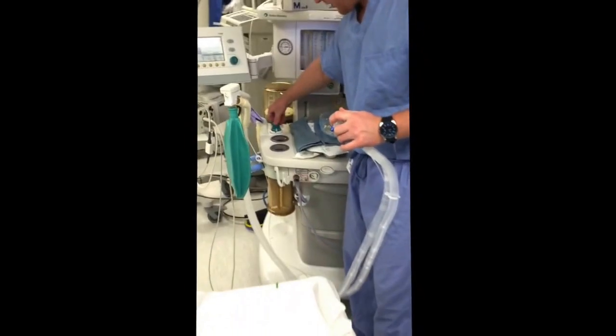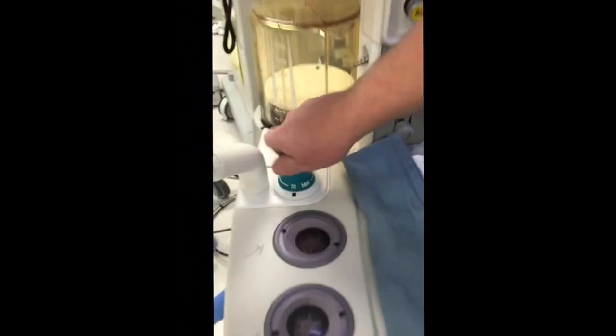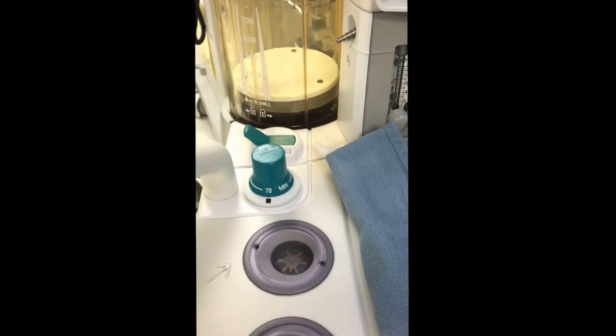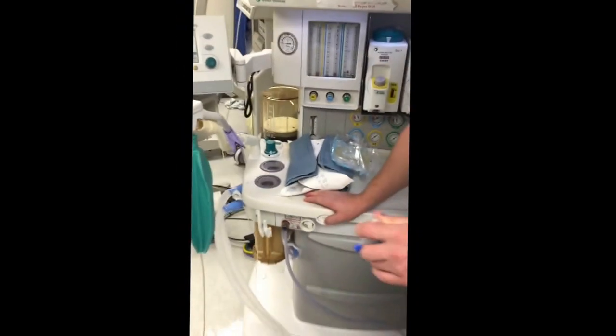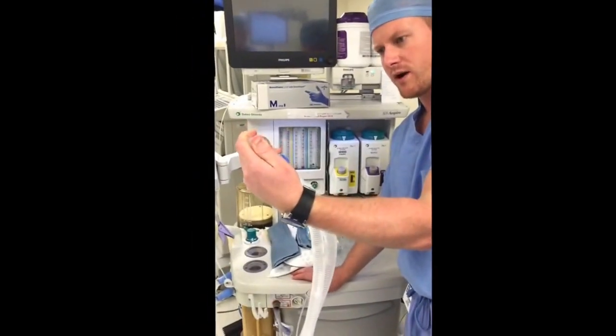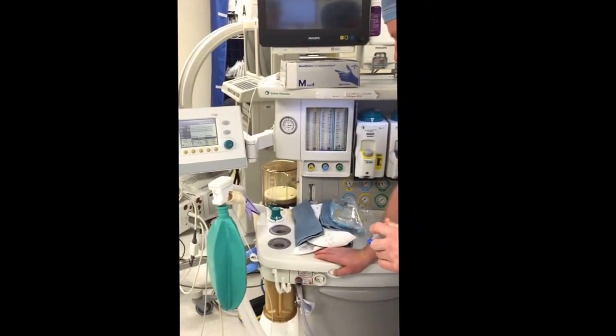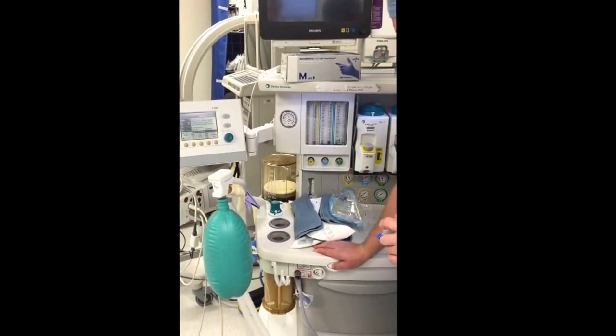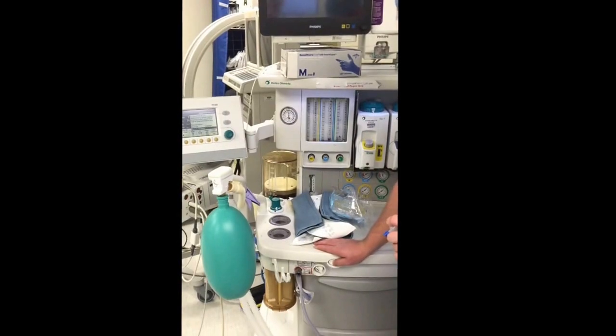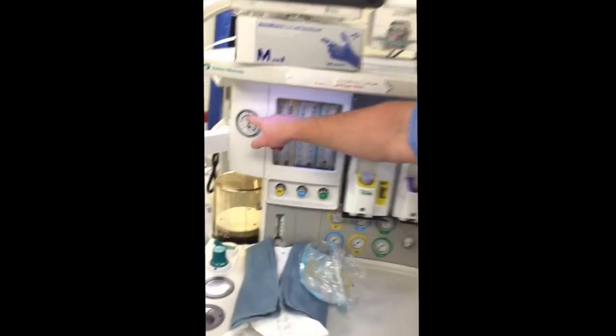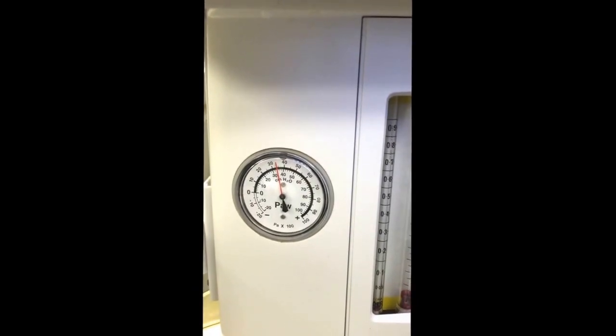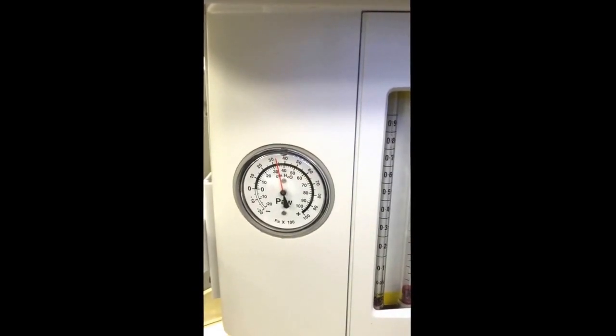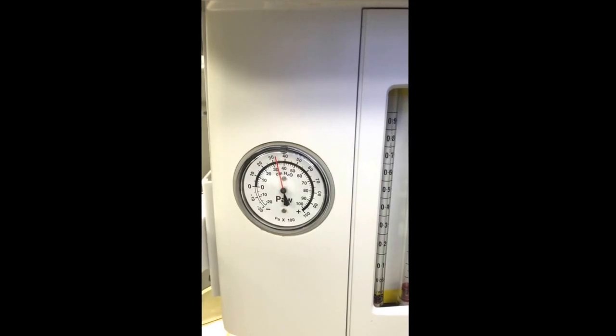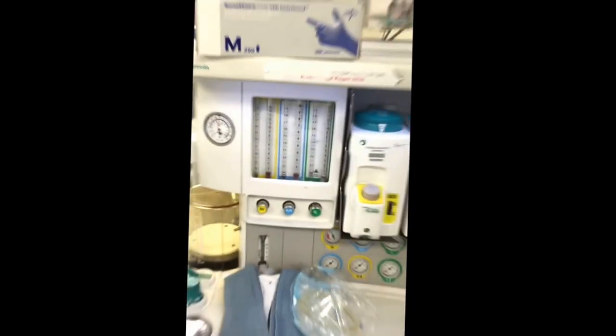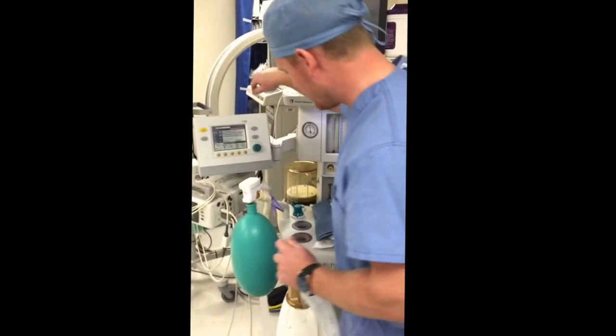Turn your APL pop-off valve all the way on. Hold your O2 flush valve and hold your thumb over the Y piece. Your goal is to get 30 centimeters water and allow it to hold that pressure for at least 10 seconds. And the next part, you can check your scavenging as well.